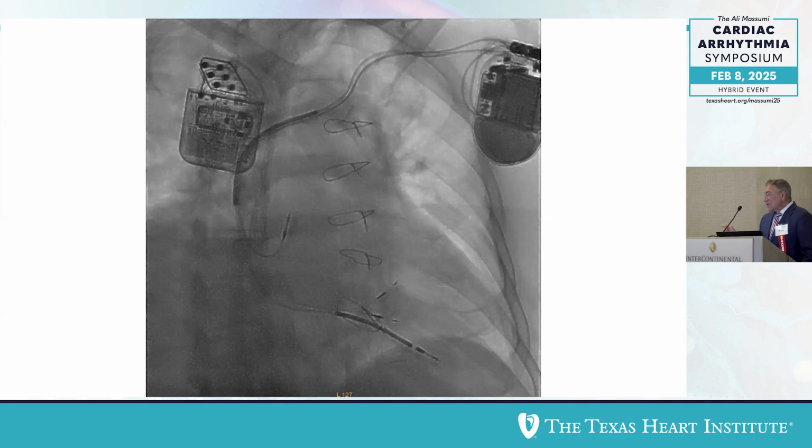When we put in a defibrillator, we set the highest output of this device and the highest sensitivity of the defibrillator, to see if there is far-field or device-device interaction.